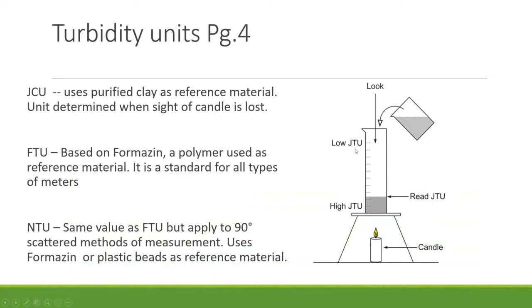The Jackson Turbidity Unit uses a transmissive device where the light source is at the bottom. You look down the center of the container as you add fluid, and when you can no longer see the candle, that's the reading — fairly primitive. Formazin units are based on a polymer standard used for all types of meters. Nephelometric Turbidity Units generate the same values as FTUs but work specifically on the 90-degree scatter method.